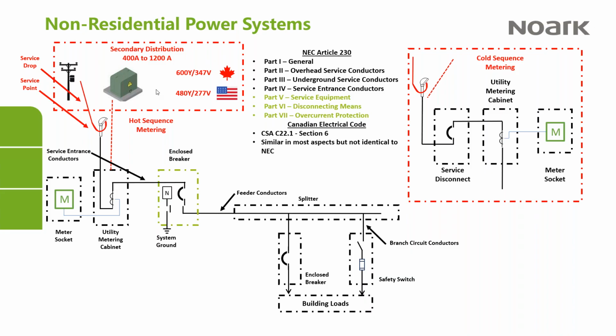Okay. Just a quick note on the cold sequence metering. As the name suggests, rather than coming directly into the metering cabinet, the circuit comes in through the service disconnect first and then into the metering cabinet. And this allows you to turn off this breaker and have no power in the metering cabinet. And again, this is totally the call of the utility on how they do it.